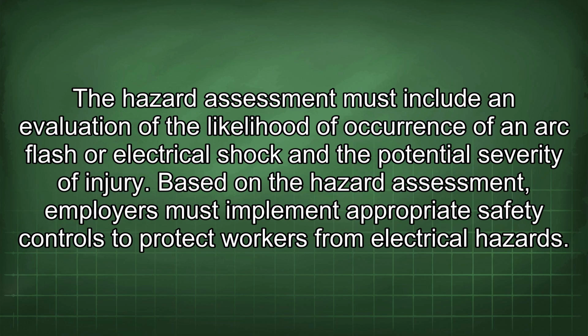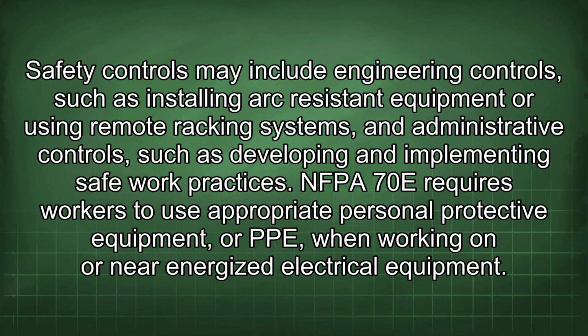Based on the hazard assessment, employers must implement appropriate safety controls to protect workers from electrical hazards. Safety controls may include engineering controls, such as installing arc-resistant equipment or using remote racking systems, and administrative controls, such as developing and implementing safe work practices. NFPA 70E requires workers to use appropriate personal protective equipment, or PPE, when working on or near energized electrical equipment.